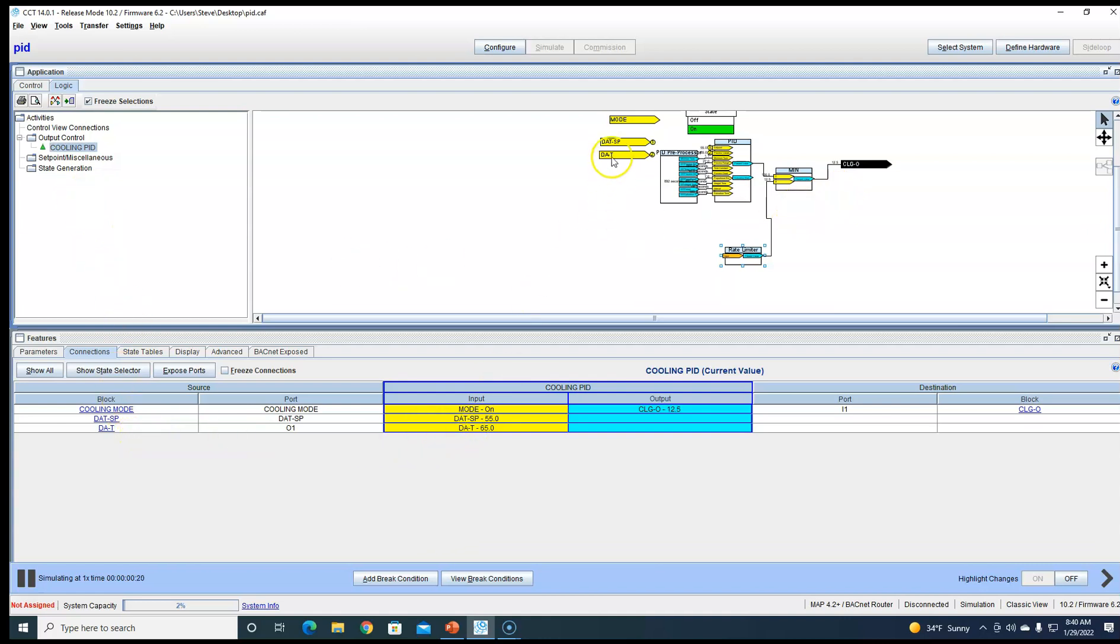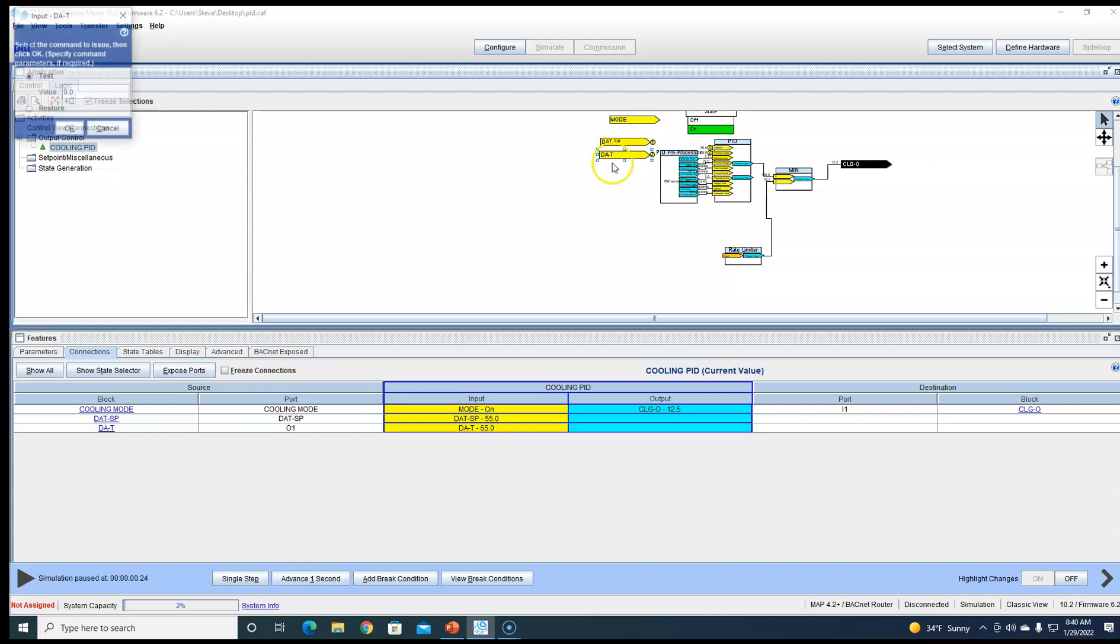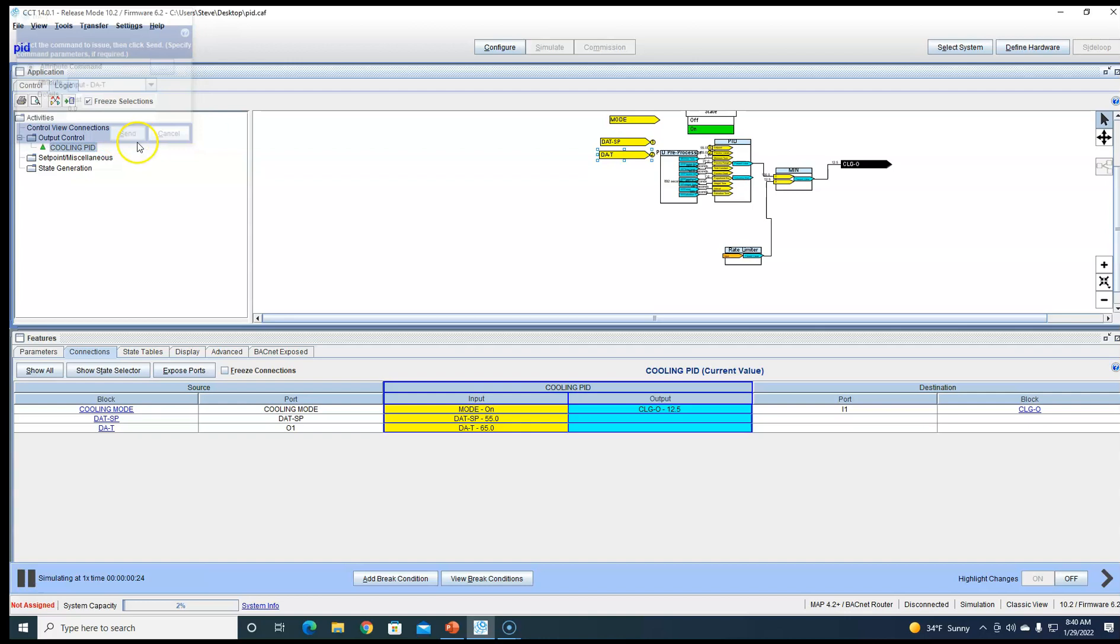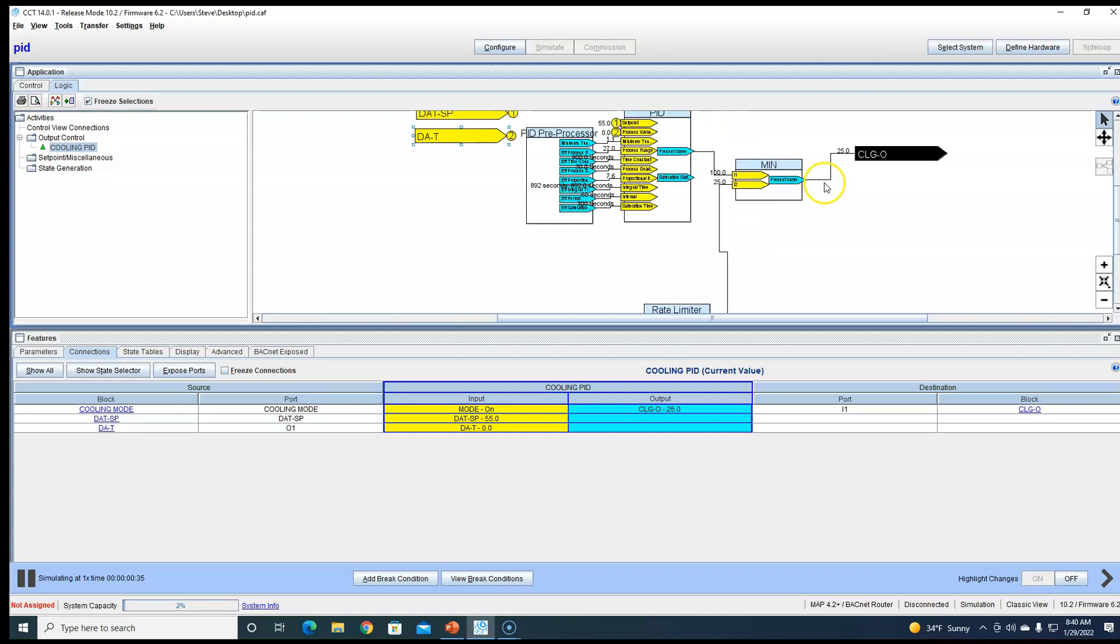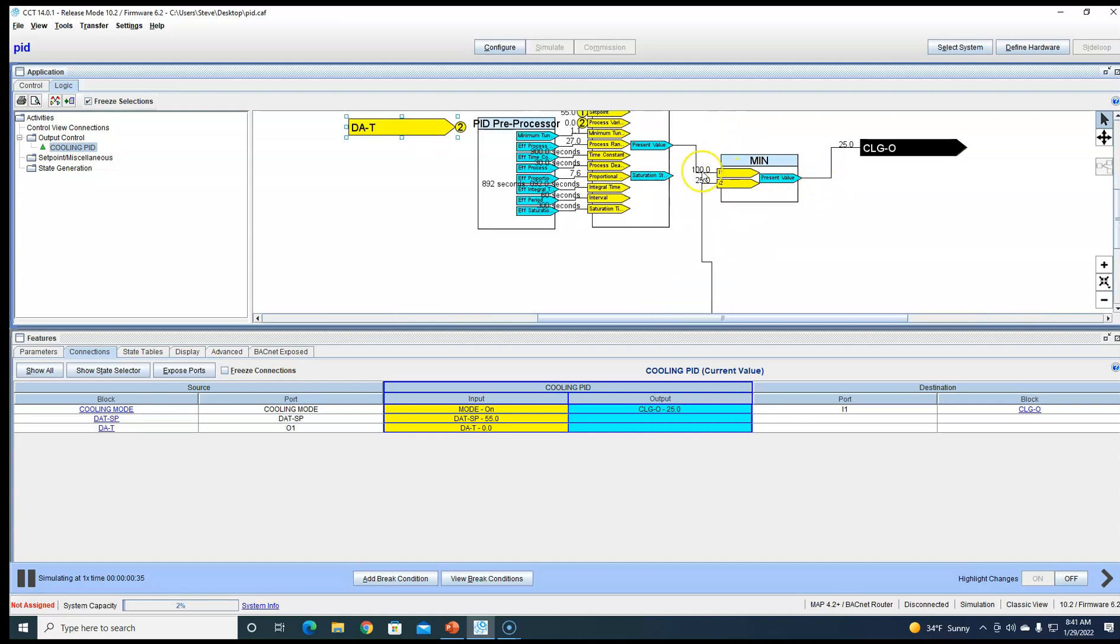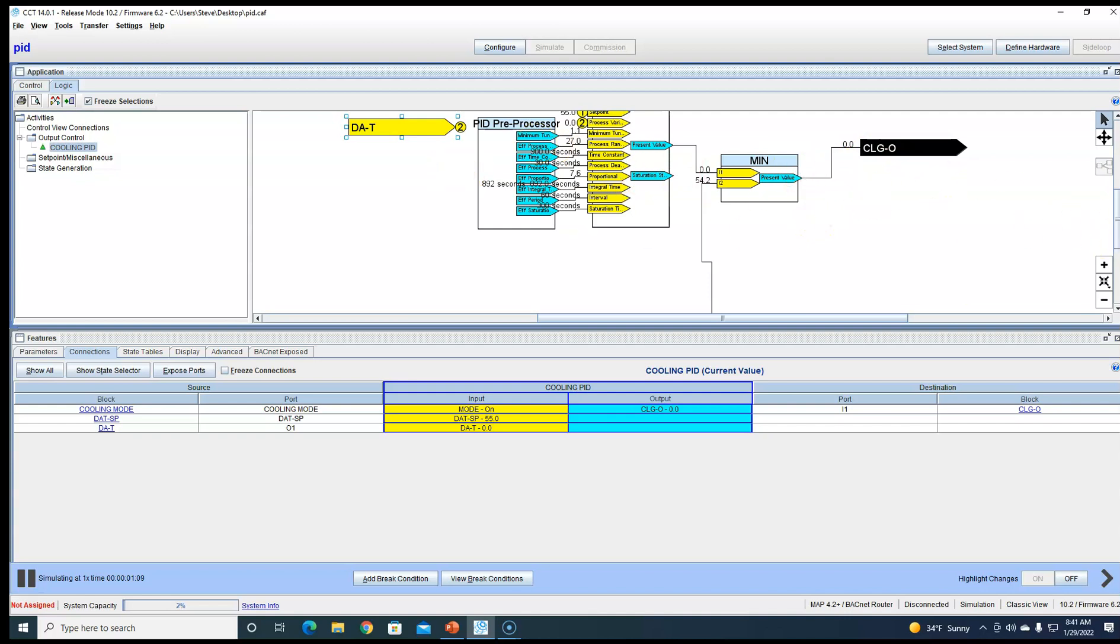But when we change our discharge air temp, it's going to go down quick. It's not going to keep it from dropping. As soon as this drops, this is going to go down just as quick as the PID does. Let the PID catch up. There it is, PID went to zero, cooling went to zero. Okay, so that's the soft start part. Only limits going up but not going down.